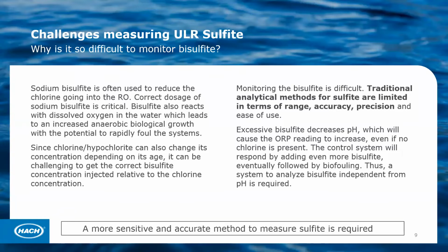So we can have sulfite reducing bacteria proliferate in our RO membranes and clog those up even faster. We also know that sulfite can cause changes in pH. It is generally an oxygen scavenger used in the boiler sort of matrix. Serves its purpose well there, but within RO membranes, it can lead to a host of other problems.